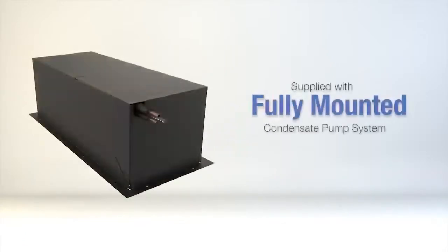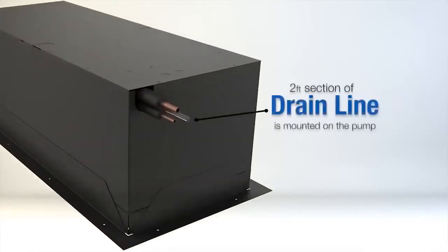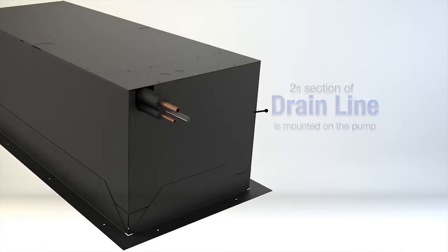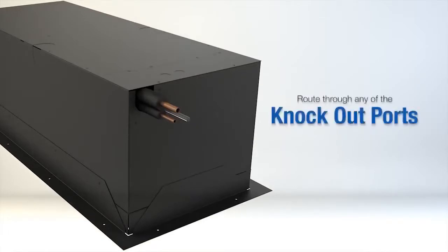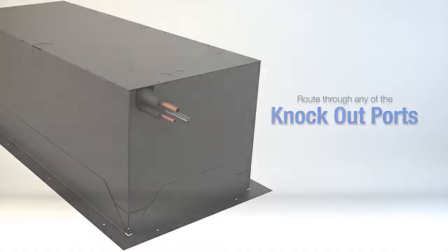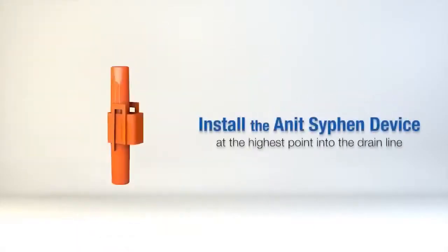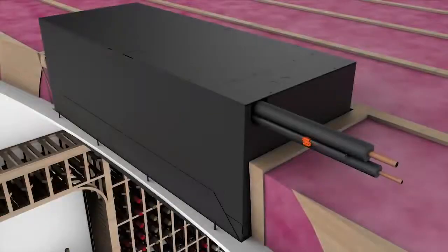Hook up the condensate pump. The unit comes supplied with a condensate pump system which is fully mounted. A 2-foot section of line is mounted on the pump so it can be routed through any of the knockout ports. It is important to install the anti-siphon device at the highest point into the drain line. This assures that water remains in the pump to keep it primed and lubricated for longevity.